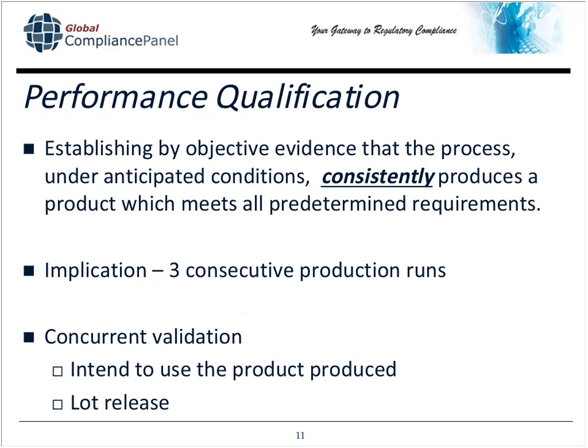If you make more equipment-based things, you're going to have to provide a statistical evaluation of why you only chose 1 or 3 or 6 units. 3 is the magic number, so to speak, but it still requires a statistical rationale for why you chose 3. What some firms choose to do in these situations is look at sales figures. Let's use 5, for example: they've shown that they sell 20 units a month, which is 5 units a week, so they're going to validate a week's worth of product. That's why they've chosen 5 units. So you can justify statistical sampling using sales figures or production figures.